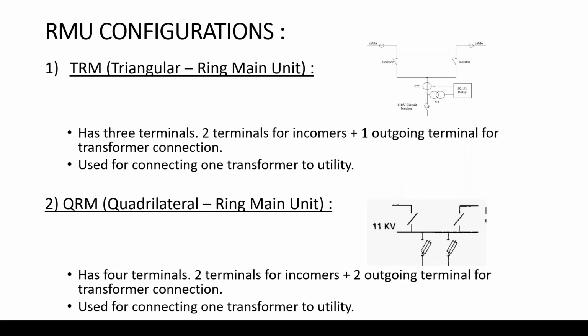The outgoing is connecting to the transformer, as you can see here, and it has all the necessary protective functions to protect the transformer. So imagine if you were connecting the transformer to the ring directly, you would not have the benefit of being able to disconnect it from the network, and you would not have the necessary protective relays in order to ensure no damage happens to the transformer in case of any fault or any short happening.